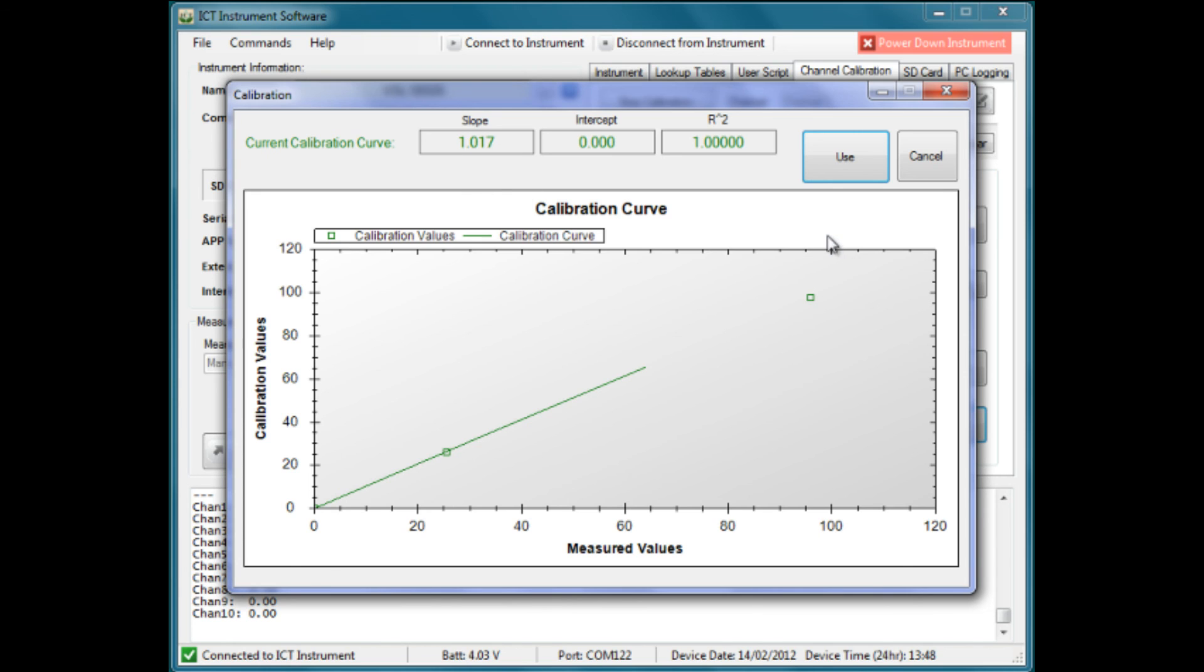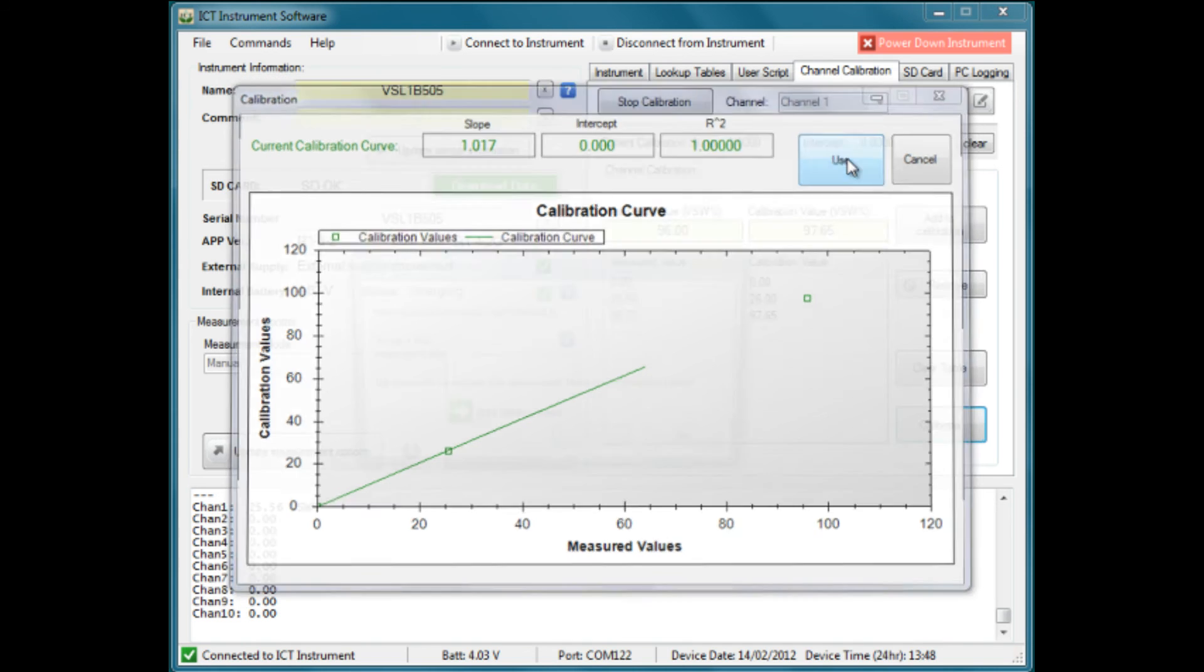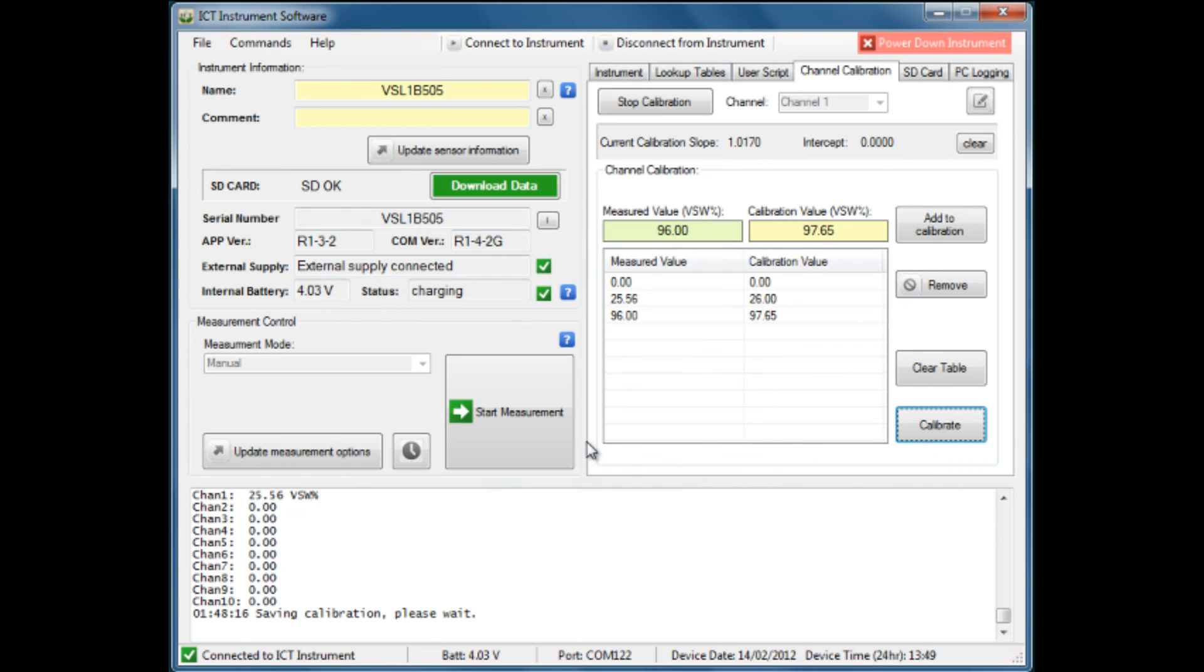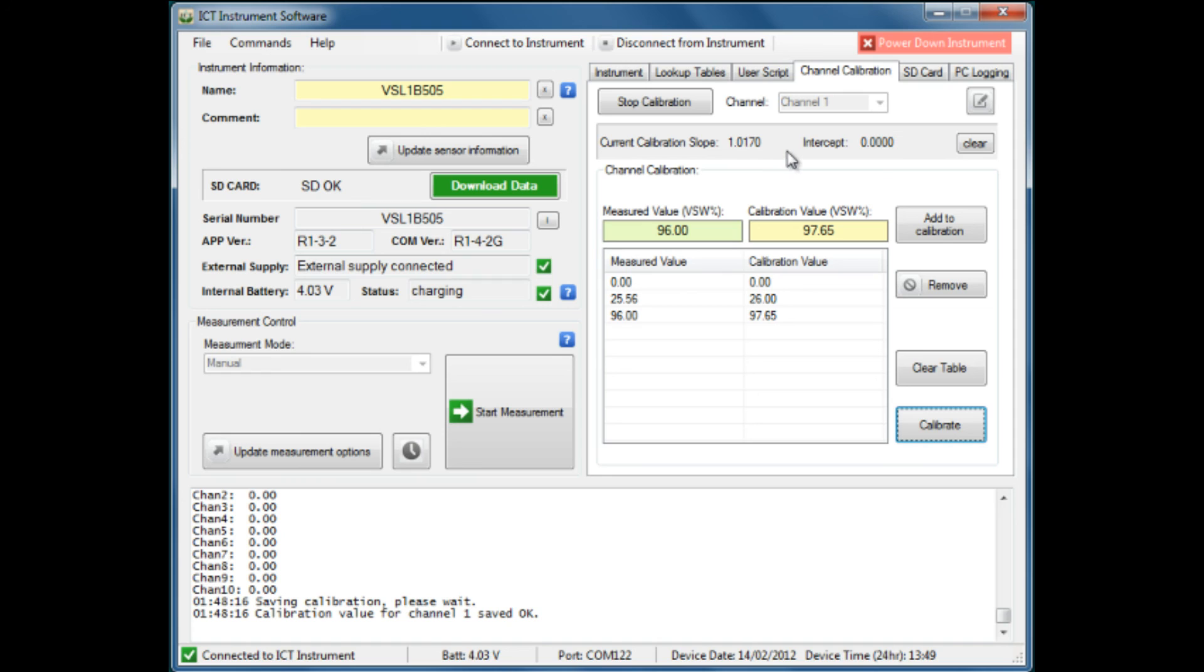If we're happy with that, we hit use, or if we feel it's not correct, we can go back and do the process again. In this case, we'll use that, and we have a confirmation that we have slope and intercept values for channel 1. We say yes, we will use that, and we notice up here that those figures have been entered for channel 1.